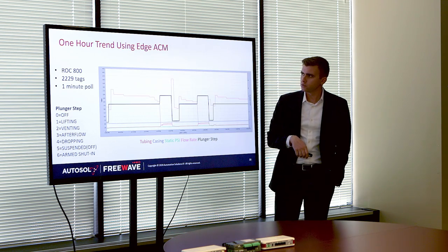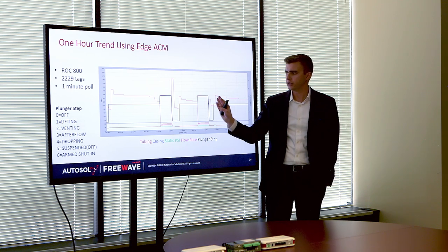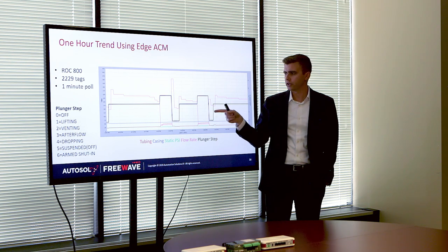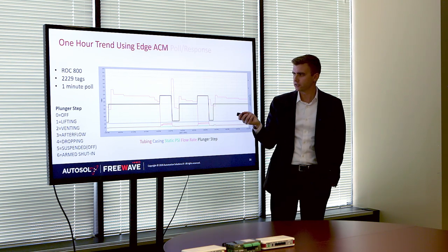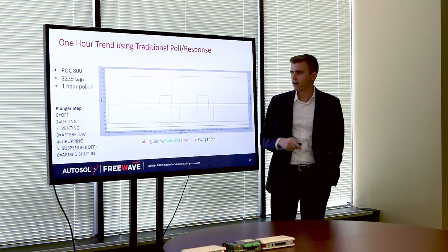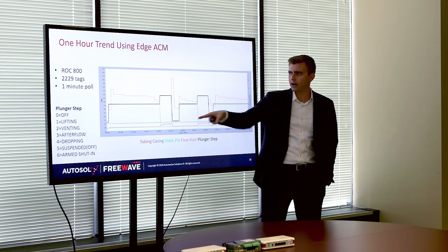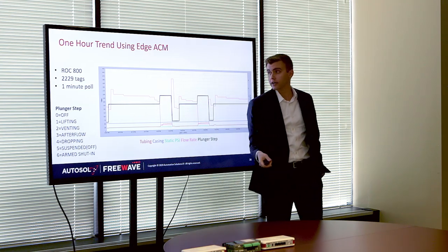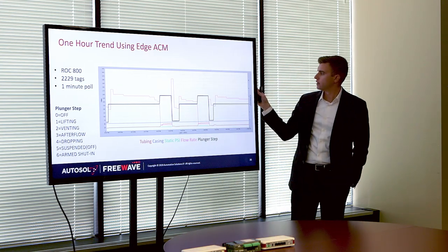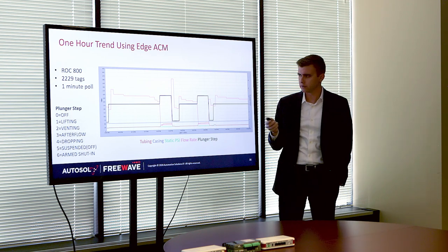Now this is what that same hour looked like using Edge ACM. The big difference is we actually caught the plunger step — we show actual activity on the plunger. The previous view had nothing on the plunger step. This is the same number of tags, but now with one-minute polling for the tags that matter. So again, 60 times the data resolution using all the same existing infrastructure.